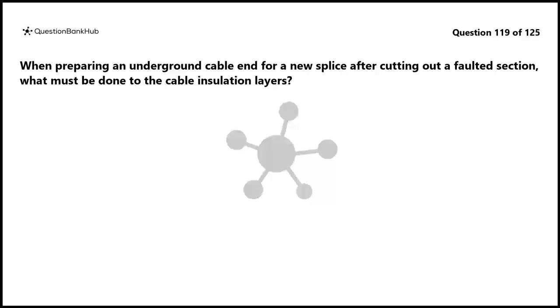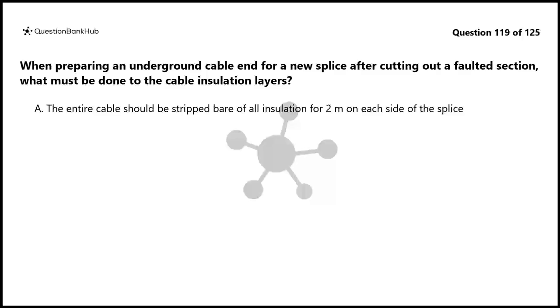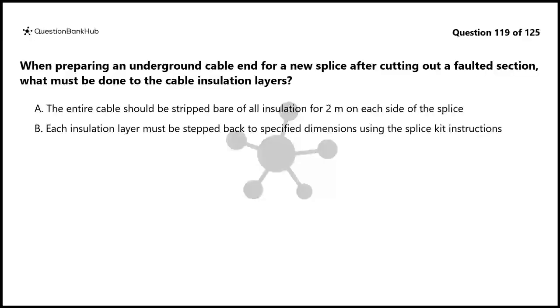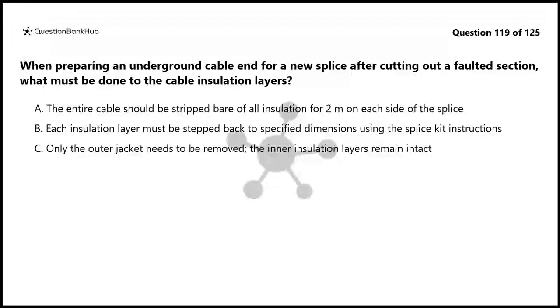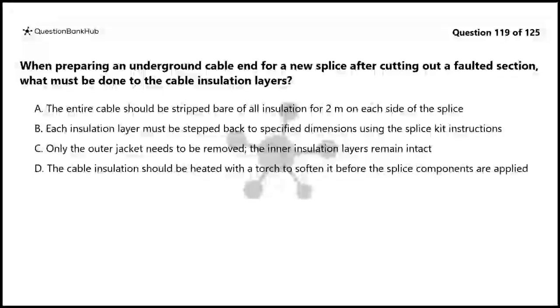Question 119. When preparing an underground cable end for a new splice after cutting out a faulted section, what must be done to the cable insulation layers? A. The entire cable should be stripped bare of all insulation for 2 meters on each side of the splice. B. Each insulation layer must be stepped back to specified dimensions using the splice kit instructions. C. Only the outer jacket needs to be removed, the inner insulation layers remain intact. D. The cable insulation should be heated with a torch to soften it before the splice components are applied.